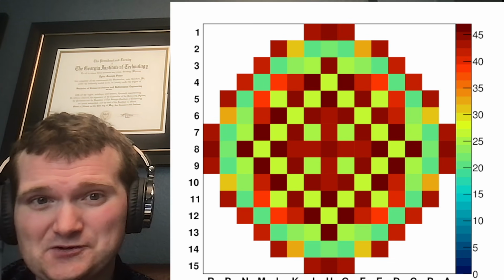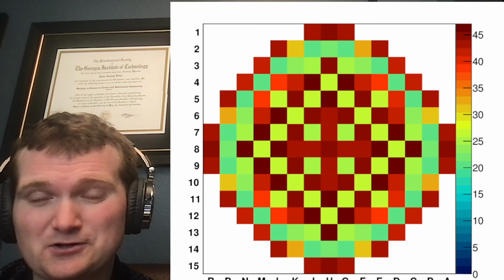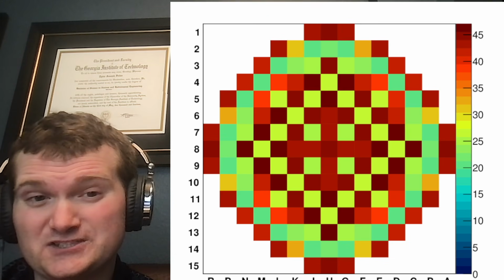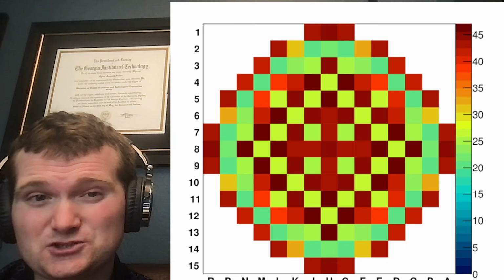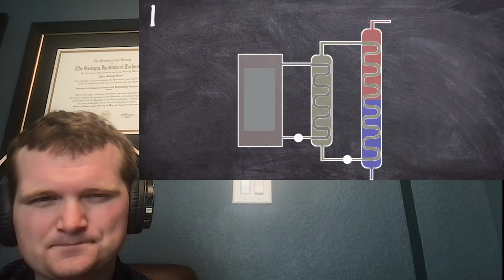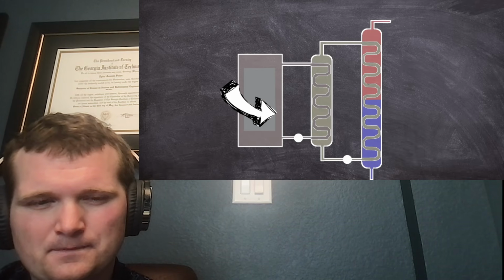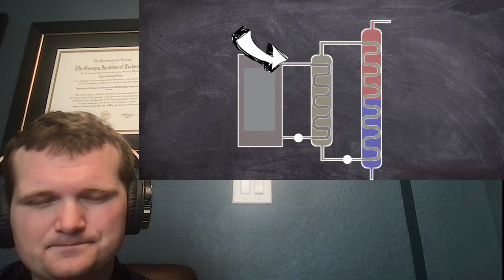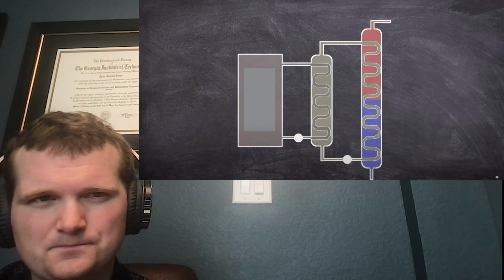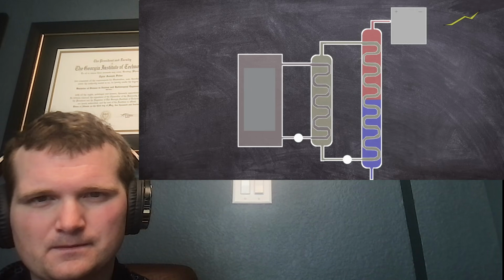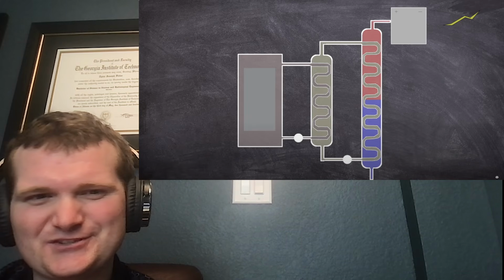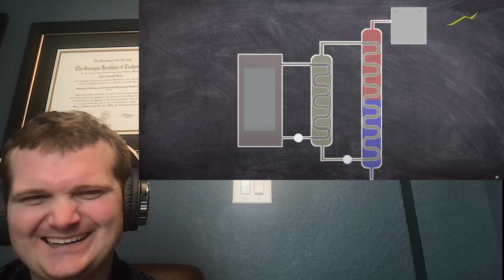And it's also low because it's inexpensive. You're not burning all of your nuclear fuel during your testing when it's not producing electricity. The reactor had 2 cooling loops, both using liquid sodium. The first loop passed through the reactor core and went through a heat exchanger, secondary loop flowing through it. The heat transferred into the secondary loop and then went through a steam generator for use with a turbine for electrical power generation. So it's interesting because we're still using good old steam.